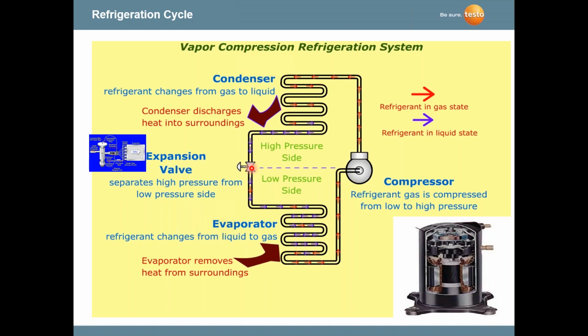The metering device is a pressure reducer and therefore drops the temperature and the pressure of the refrigerant as it travels to the evaporator. Now the refrigerant is cold, or another term would be it has less heat, as it enters the evaporator. Once we get into the evaporator, there is more heat in the room air as it passes over the evaporator coil, and the heat is being transferred to the refrigerant from the distribution air. As a result, the refrigerant is going to boil and change from a liquid to a vapor.